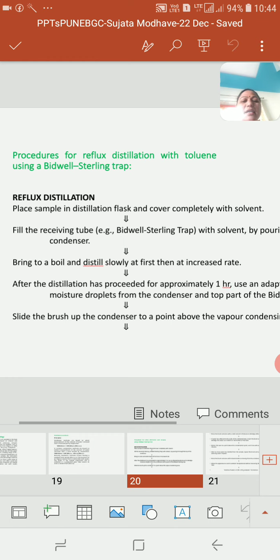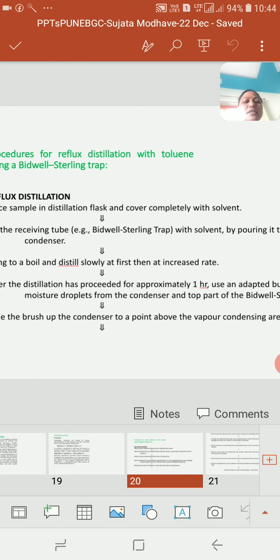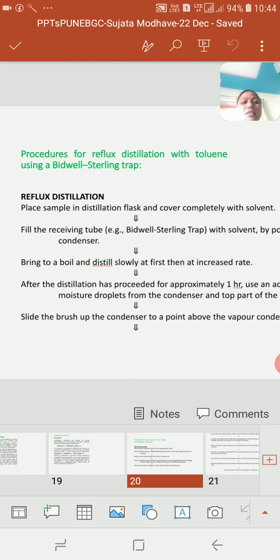After the distillation has proceeded for approximately 1 hour, use an adapted burette brush to dislodge moisture drops from the condenser and draw them to the top part of the Bidwell-Sterling trap. Then the next step is to slide the brush up the condenser to a point above the vapor condensation area. Next, rinse the brush and the wire with a small amount of toluene to dislodge the adhering water drops. Then if water has adhered to the wall of the calibrated tube, invert the brush and use the slightly bent wire to dislodge the water. It is collected at the bottom of the tube.